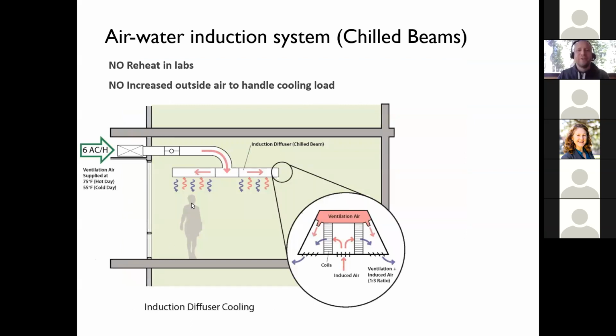But I'm going to quickly walk you through how we use chilled beams and how they can provide cooling to the space. So on Monday, Gail talked about separating ventilation systems from heating and cooling, where we have a DOAS system, dedicated outdoor air, that just provides ventilation air to the space. And then we have some other element that's providing the sensible heating and cooling to the space. So chilled beams are an example of that.